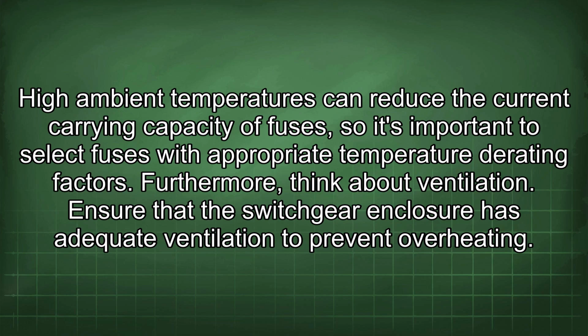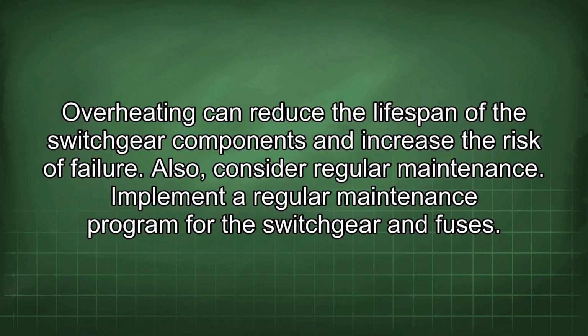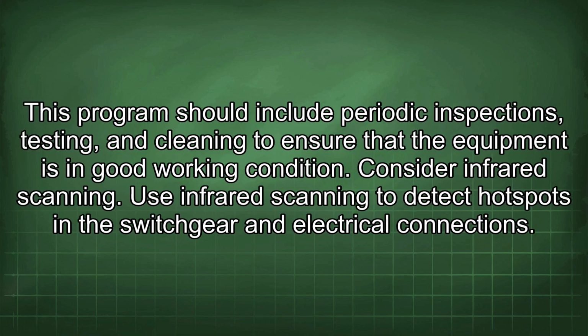Ensure that the switchgear enclosure has adequate ventilation to prevent overheating. Overheating can reduce the lifespan of the switchgear components and increase the risk of failure. Also, consider regular maintenance. Implement a regular maintenance program for the switchgear and fuses. This program should include periodic inspections, testing, and cleaning to ensure that the equipment is in good working condition.